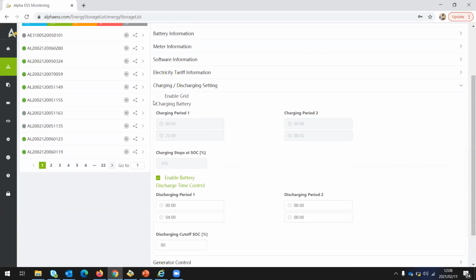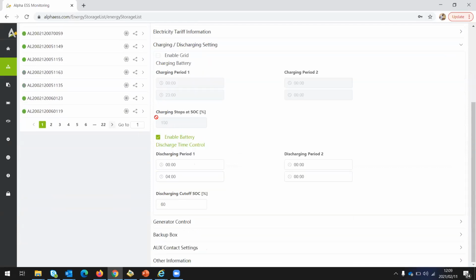So on this one, you can set your inverter to charge. You get 2 charging periods, so you can set it to charge for a certain period of time, maybe in the morning on time 1, and in the evening on time 2. You can set it to discharge for certain periods of time, with preferential. So this system is set to discharge the battery only at 12 to 4.